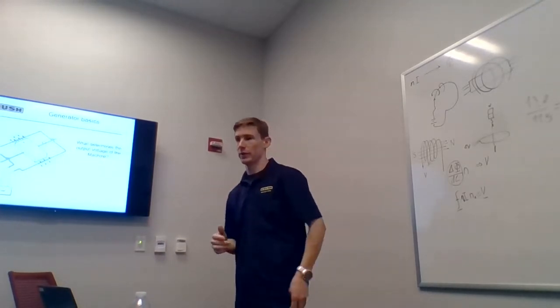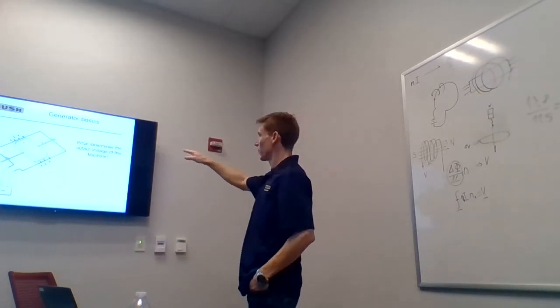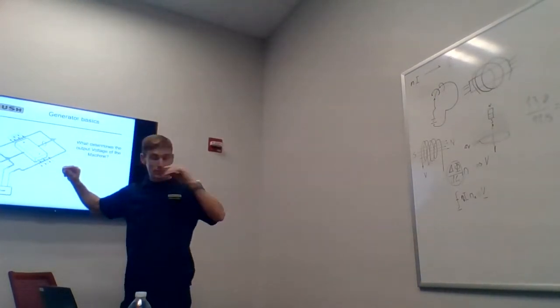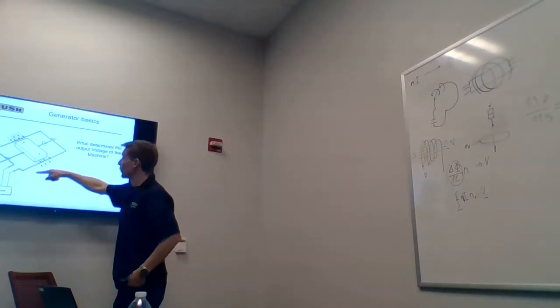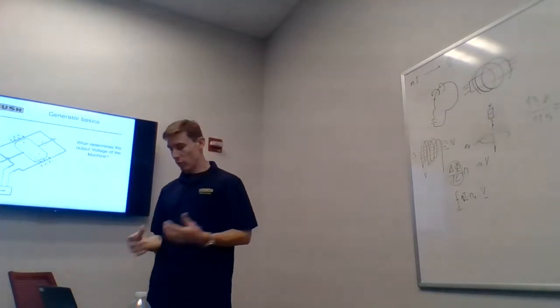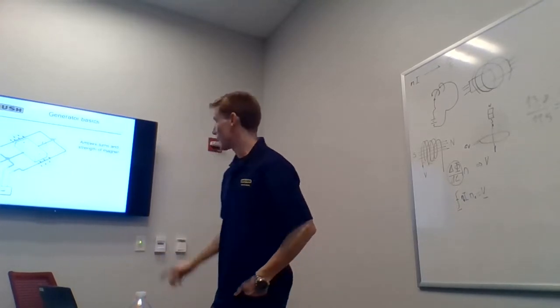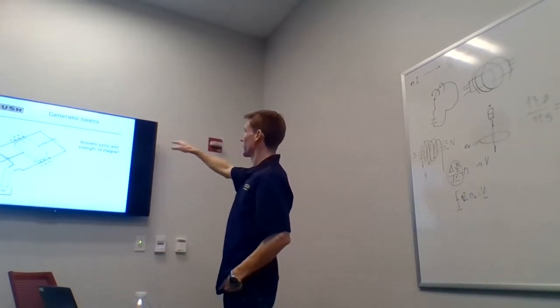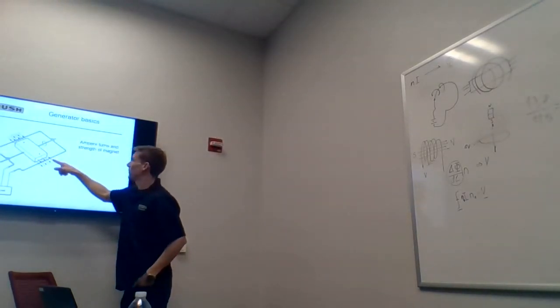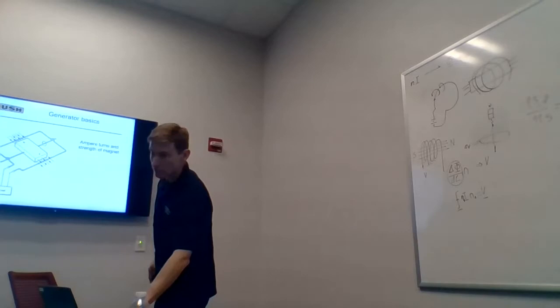What determines the output voltage of the machine? It's determined by the speed, how many turns you have, and the strength of the magnets — all of this adds voltage to the output. It's what's called ampere-turns and the strength of the magnet — the main magnetic flux — and how many turns you have. The same principle as a transformer.